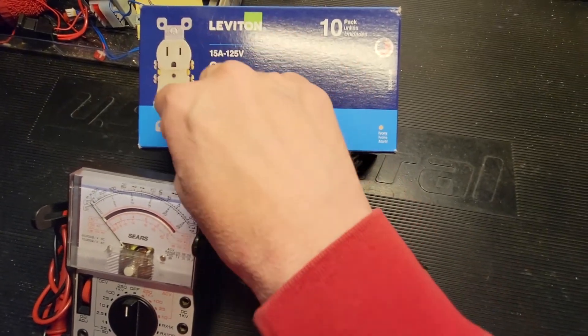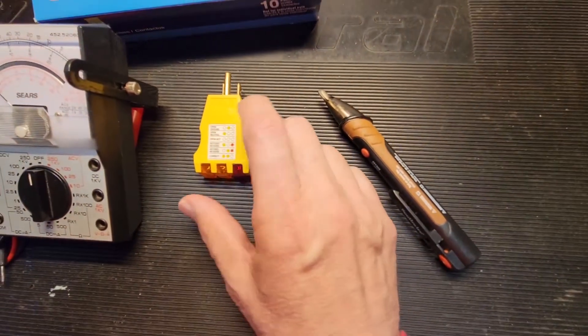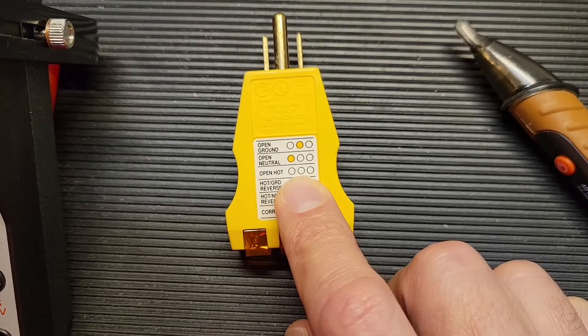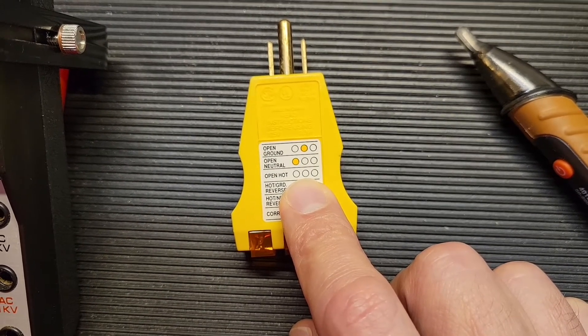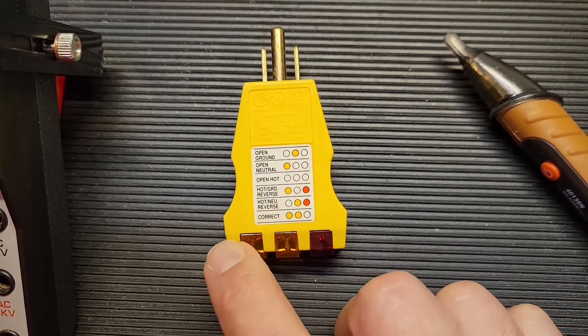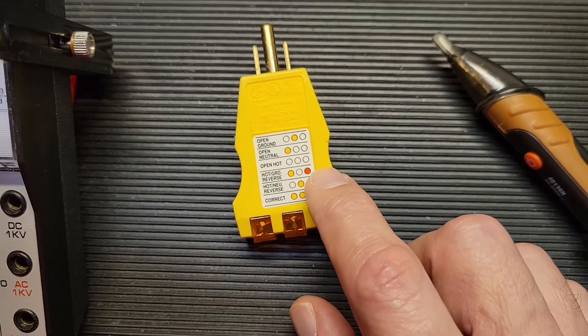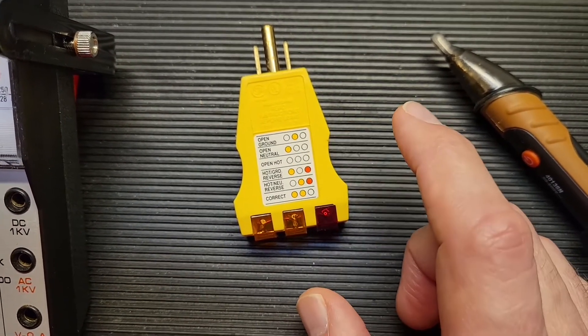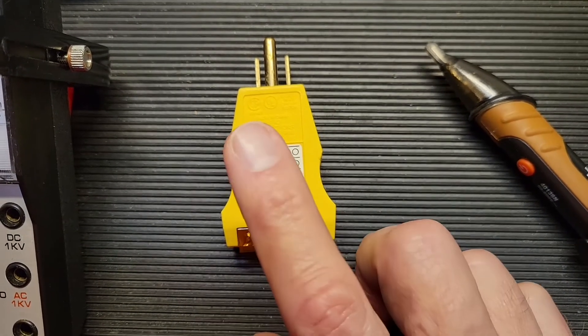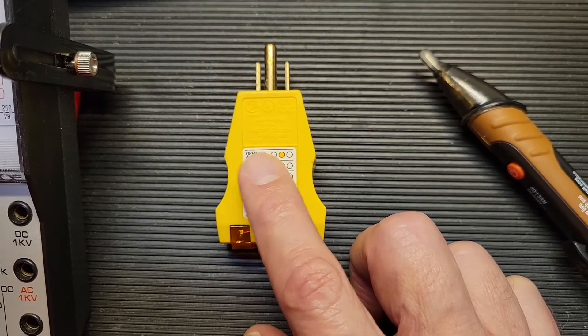The socket tester, while a great diagnostic tool because it can tell you whether there's a reversed hot neutral, has the problem that an open hot is indicated by no lights, which is the same indication that you would get if the power was off to that plug. So you don't know for sure if you're looking at an open hot or no power. I want to be 100% certain that there is no voltage going into that plug when I'm working on it.